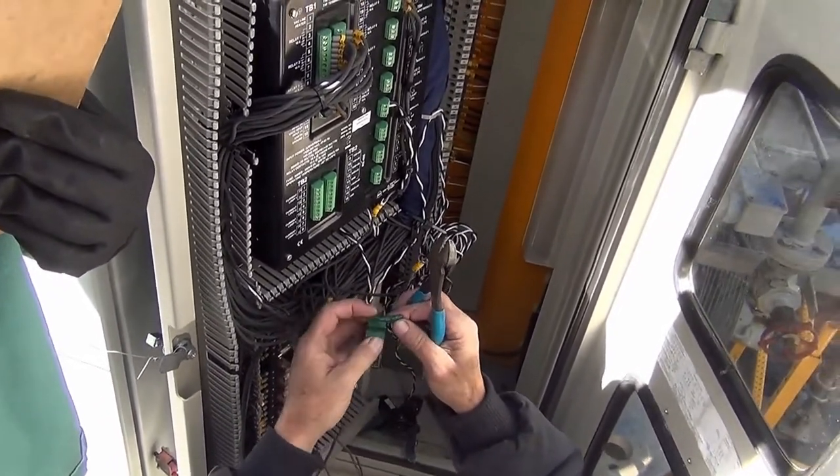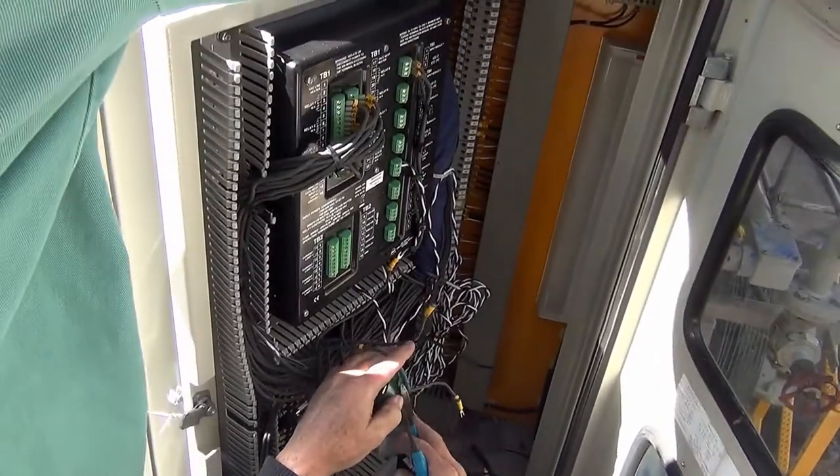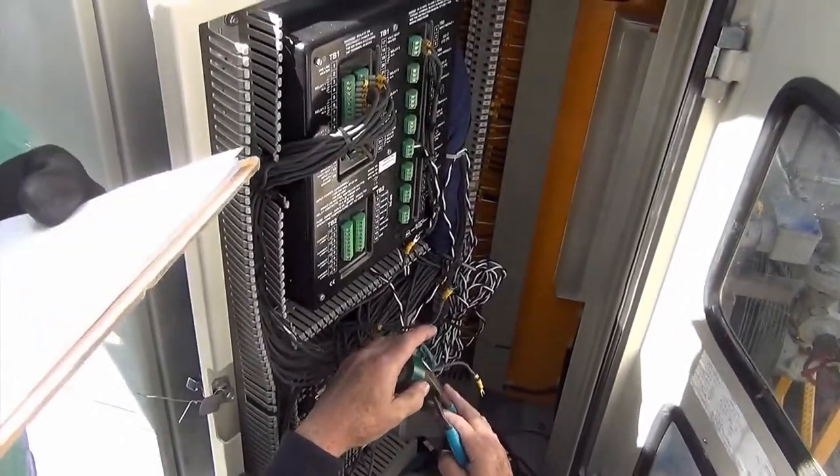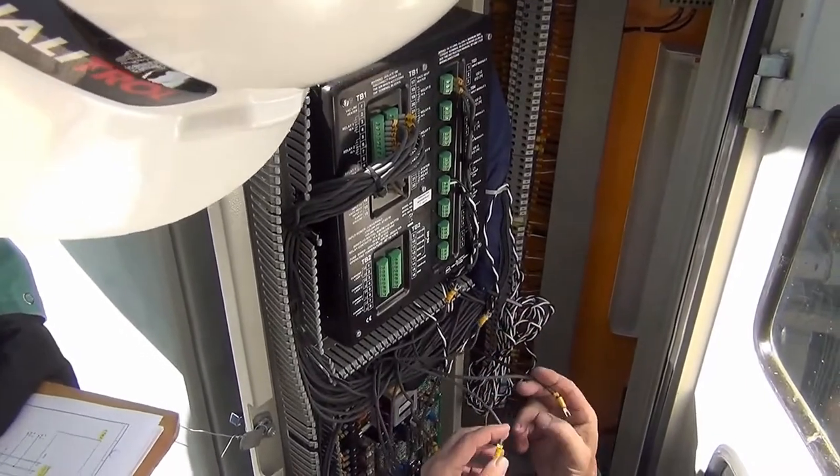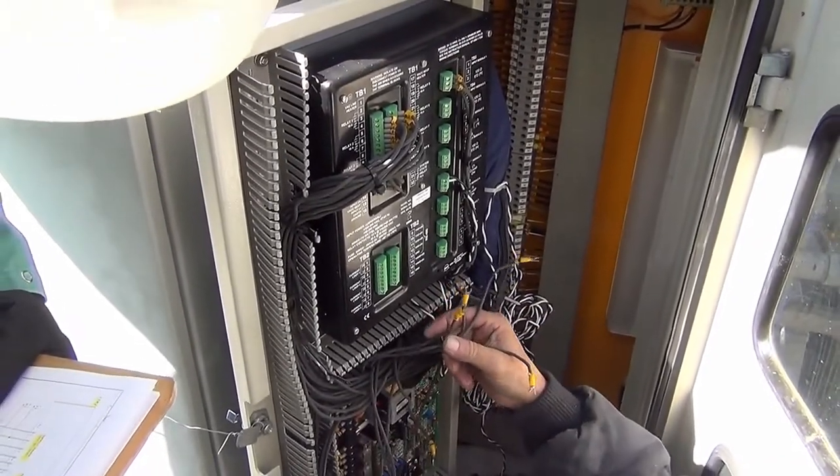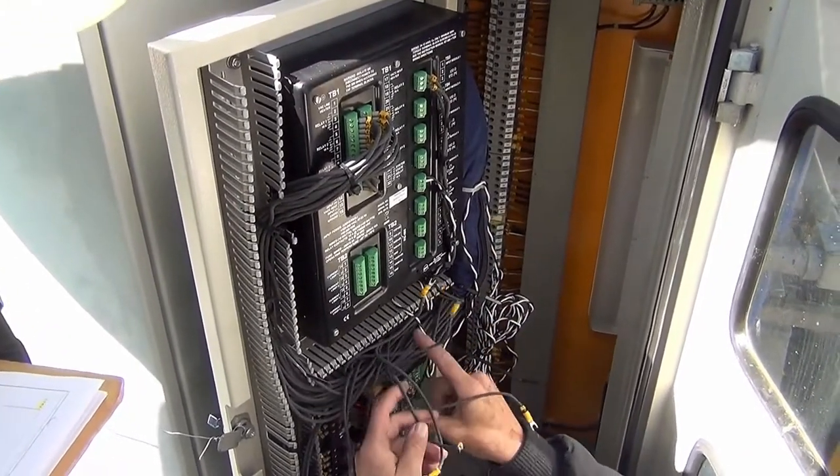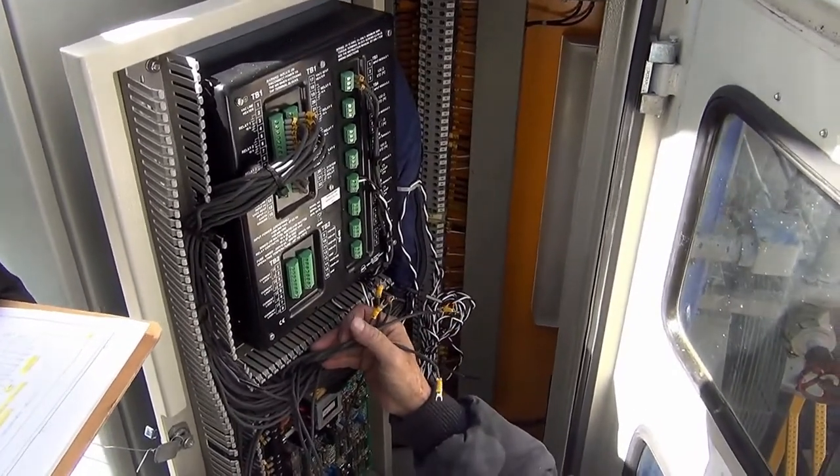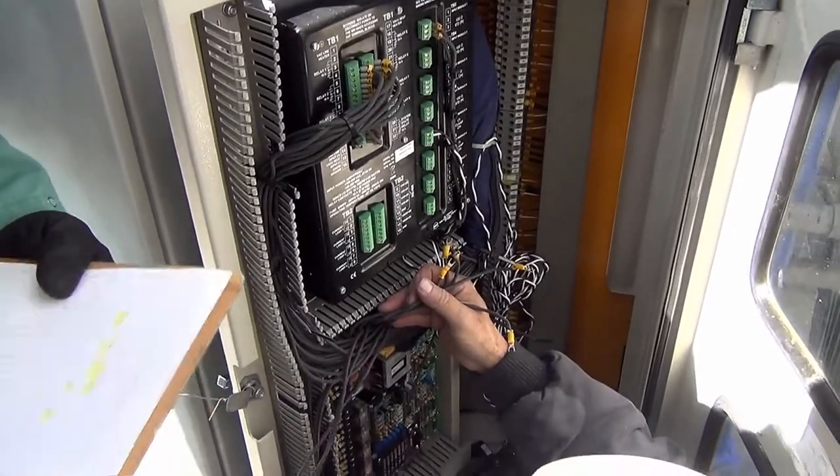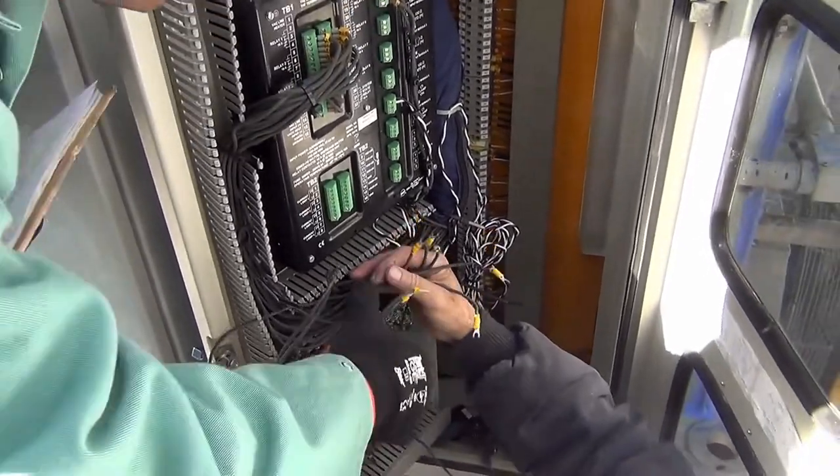If you have any analog output loops that you would like to connect and make it communicate with your SCADA system, you can use terminal TB2, terminals 1 through 8, to utilize any of the four output loops that the 509 ITM comes with. You can change the set points and the control signal of these output loops using the remote ITM software.